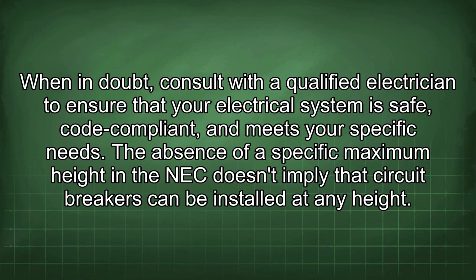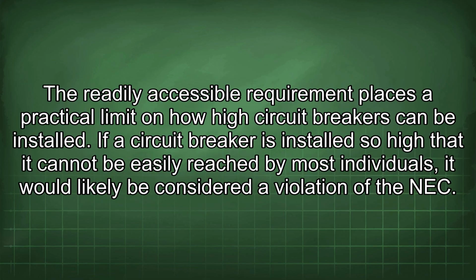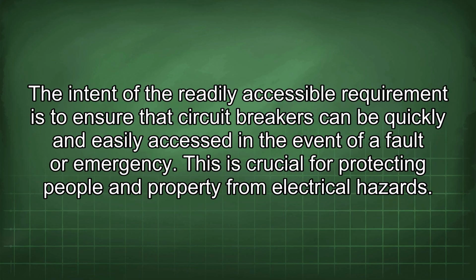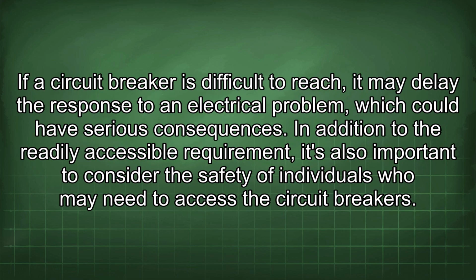The absence of a specific maximum height in the NEC doesn't imply that circuit breakers can be installed at any height. The readily accessible requirement places a practical limit on how high circuit breakers can be installed. If a circuit breaker is installed so high that it cannot be easily reached by most individuals, it would likely be considered a violation of the NEC. The intent of the readily accessible requirement is to ensure that circuit breakers can be quickly and easily accessed in the event of a fault or emergency. This is crucial for protecting people and property from electrical hazards. If a circuit breaker is difficult to reach, it may delay the response to an electrical problem, which could have serious consequences.